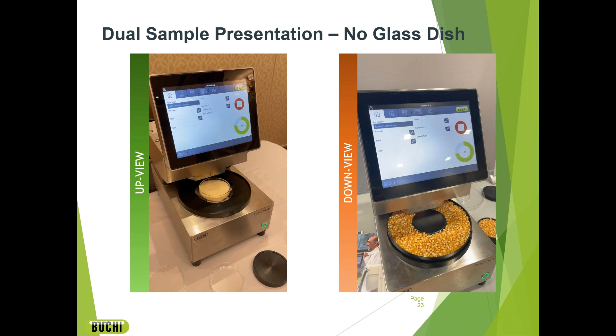One more thing, we measure color. Surprise! Speaking of options, the BUCHI Proximate can either be NIR only or have a combined NIR and visible spectrometer. Now, with a combined spectrometer and detector, it is possible to measure color directly using the visible region of the spectrum or as a calibration against a primary method for measuring color, e.g. the Hunter method. In addition to illumination options, the unit offers all three common metrics for color spaces, that is LAB, LCH, and XYZ. Now, color may provide useful insights into sample properties. For instance, in the LAB color space, a high L value in flour could be an indicator of low ash, while a low L value signifies the opposite.